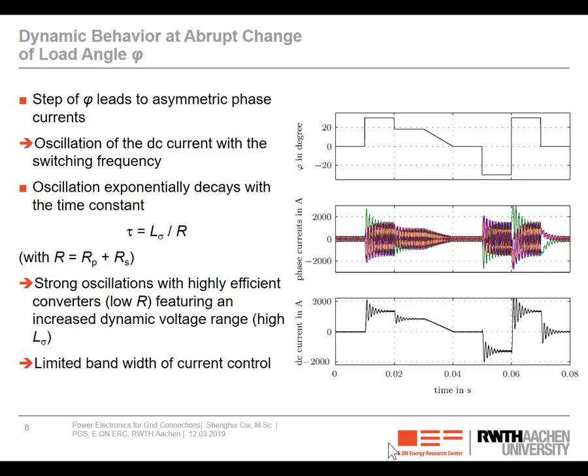And that is the case because of the damping effect of the transformer resistances. Here the damping speed, tau, is defined by the transformer leakage inductance and the transformer resistance. One interesting feature of power electronics is that the higher the power rating, the higher the efficiency. So a power converter with a power rating of several megawatts is extremely efficient, so we have a very, very small resistance. It means it takes a lot of time until this inrush current fully decays.